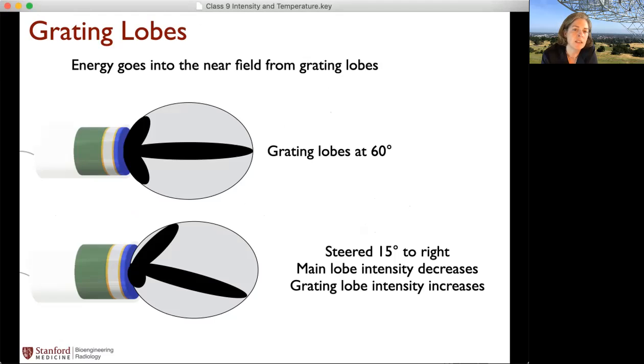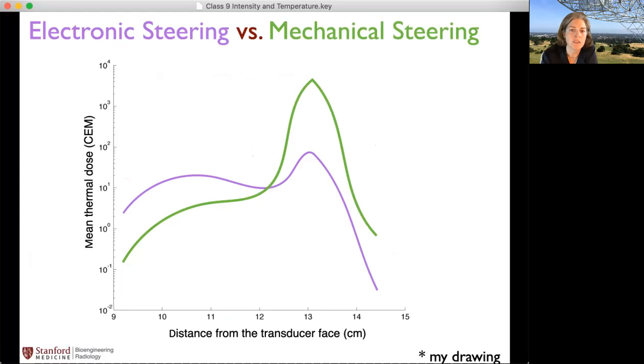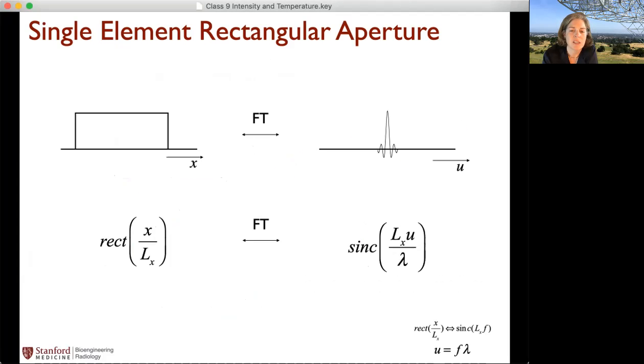If you're mechanically steering, then you're always pointing straight out. These grating lobes are staying relatively small. If you're electronically steering, now the grating lobe's going to increase. And then the main lobe might be decreasing. So that's the reason here. Why is the main lobe amplitude smaller? Well, that's the same thing as that main lobe is decreasing.